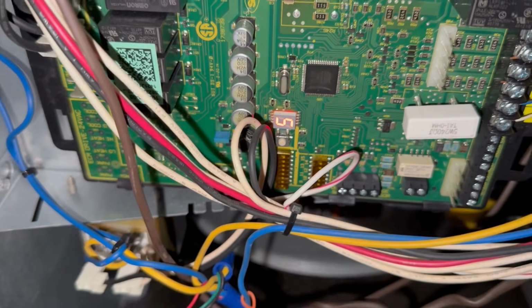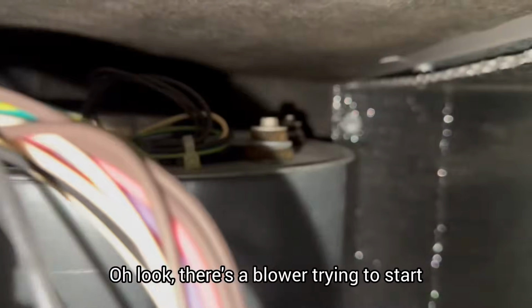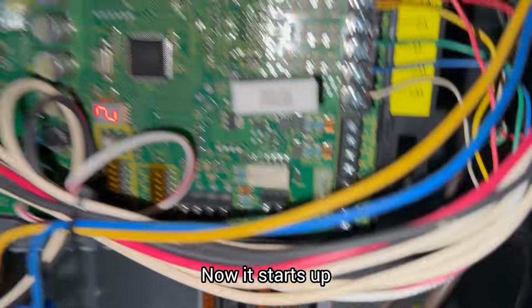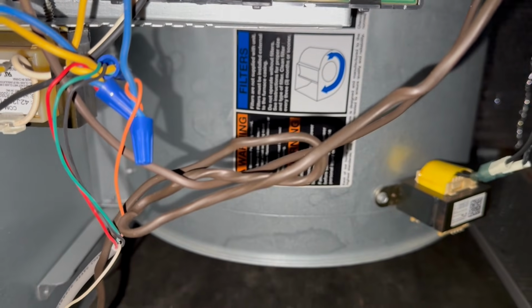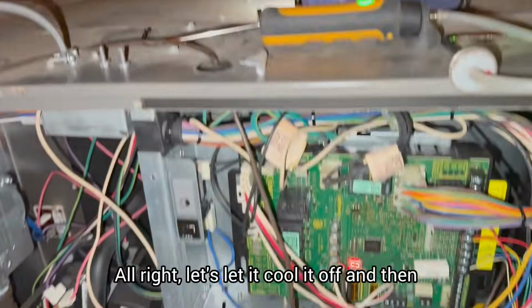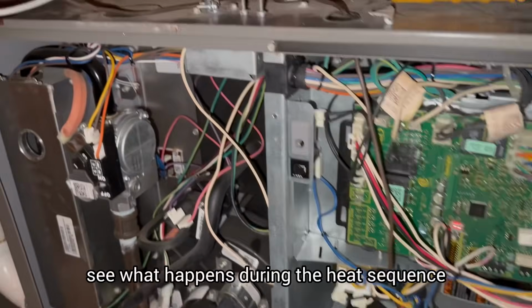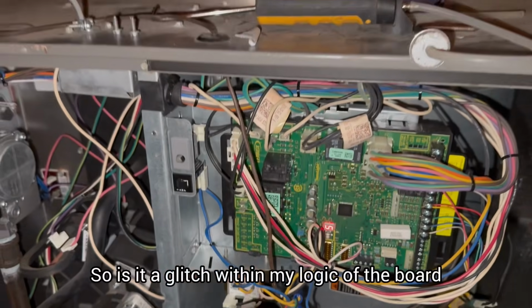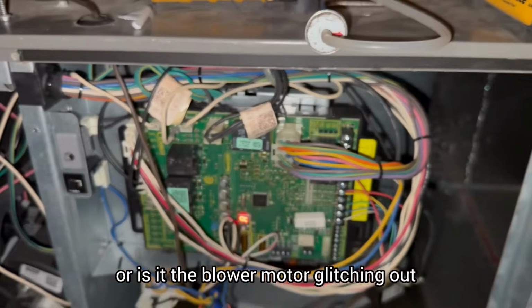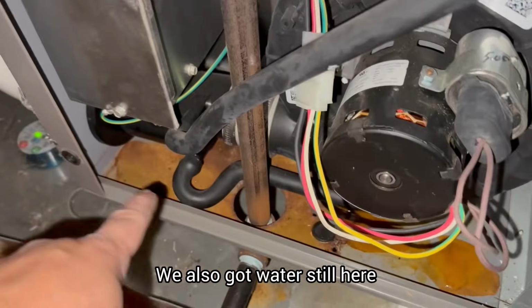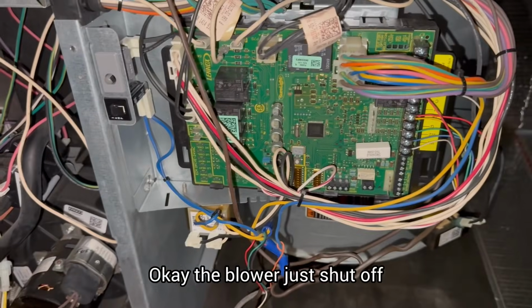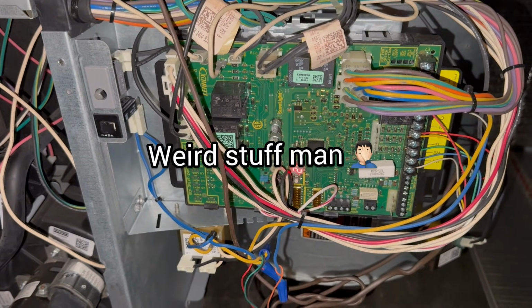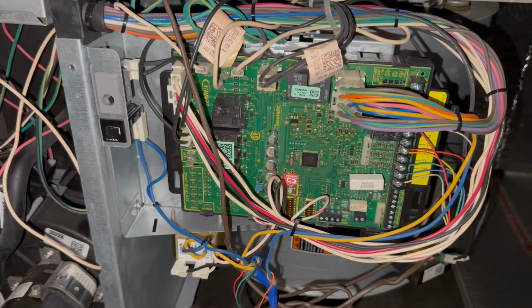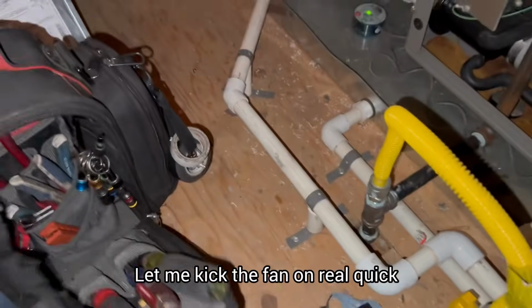E250. Oh look, there's the blower trying to start. Now it starts up. Alright, let's let it cool off and then see what happens during the heat sequence. So is it a glitch within the logic of the board, or is it the blower motor glitching out? That's what we're gonna have to find out. We also got water still here. Okay, the blower just shut off. Let me kick the fan on real quick. Let's see if I can get this motor to start again.